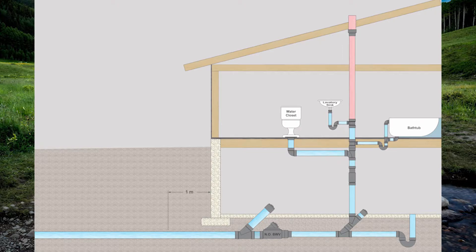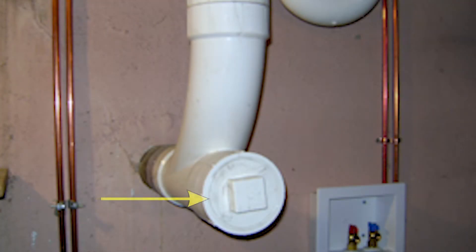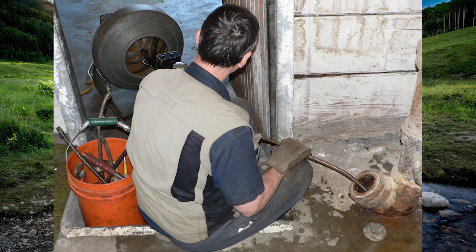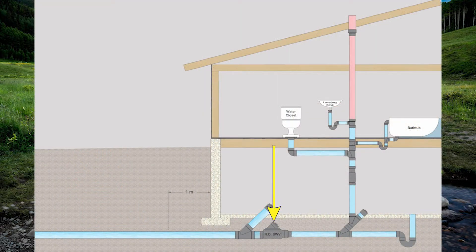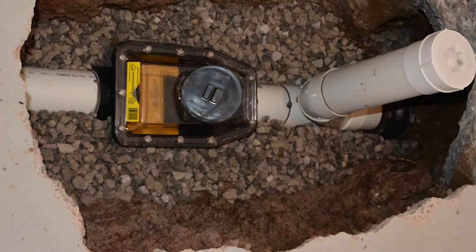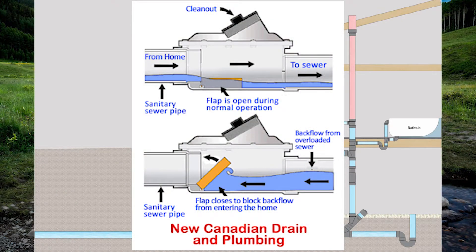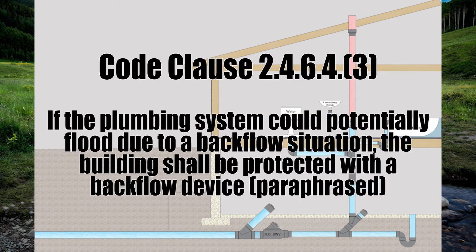Before we get to that main stack, let's talk about the two devices in the building drain. The first is the main clean out — a removable cap so you can get cleaning equipment down into the pipe to clear blockage. The next device is a normally open backwater valve. This device only allows drainage to flow in the proper direction, from the house out to the city main, but if the city main were to back up, this check valve will close, stopping that sewage from backing up into your house.